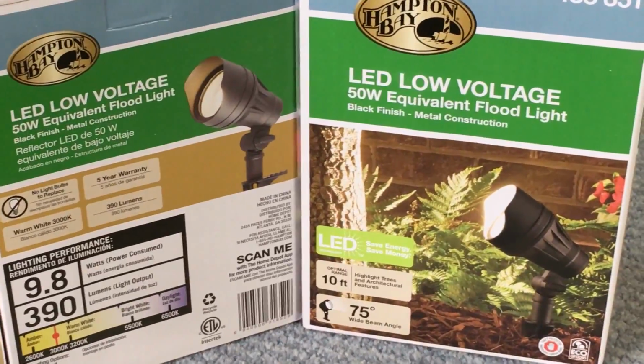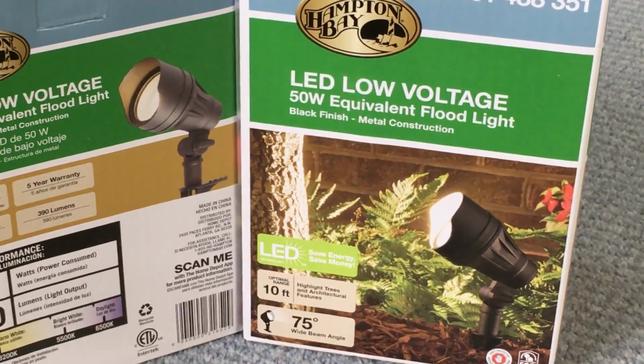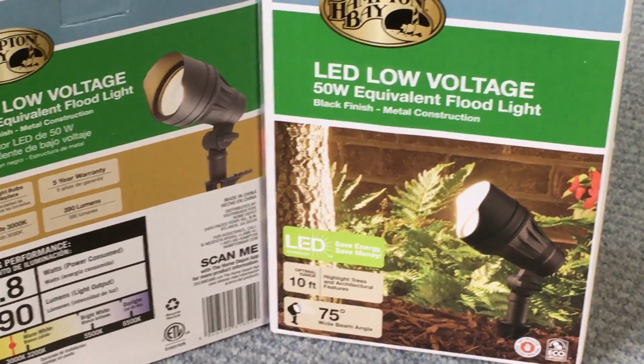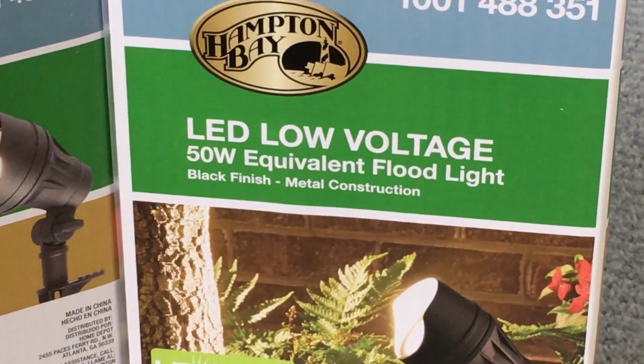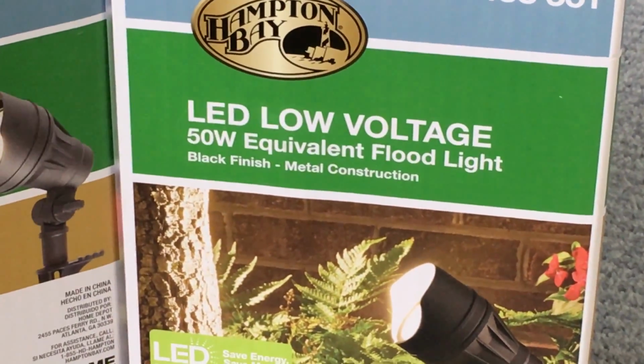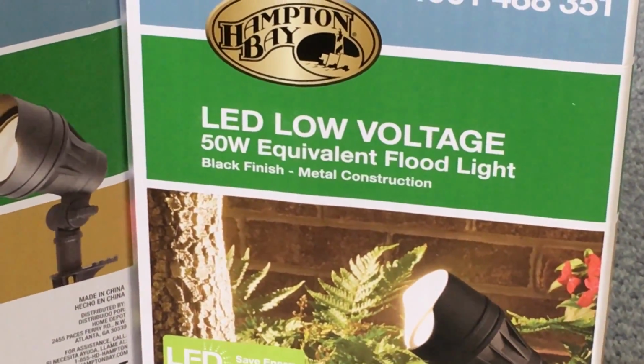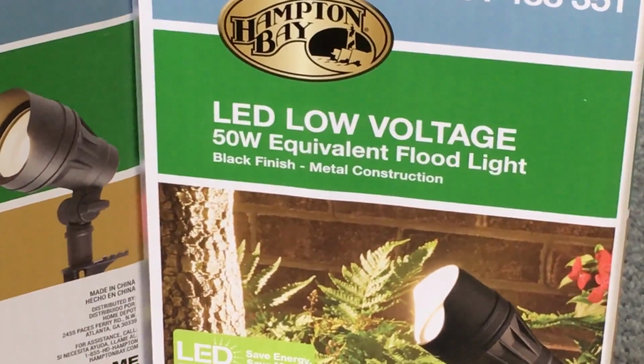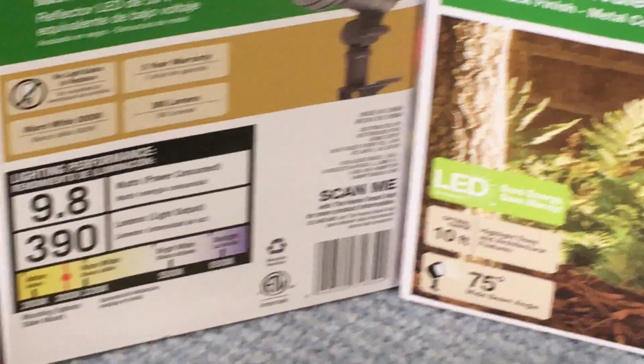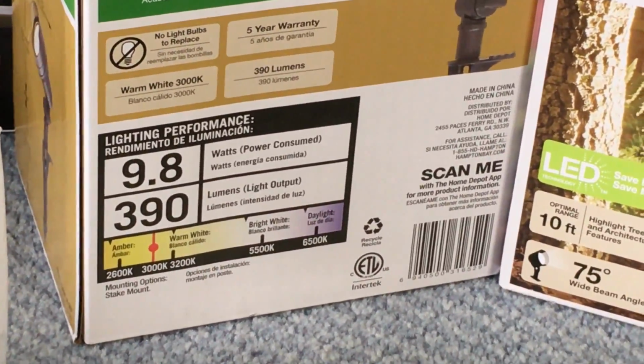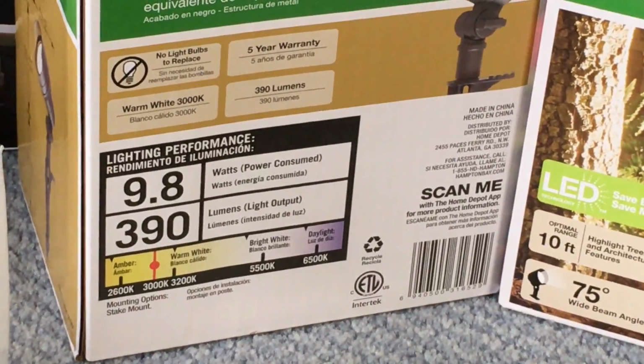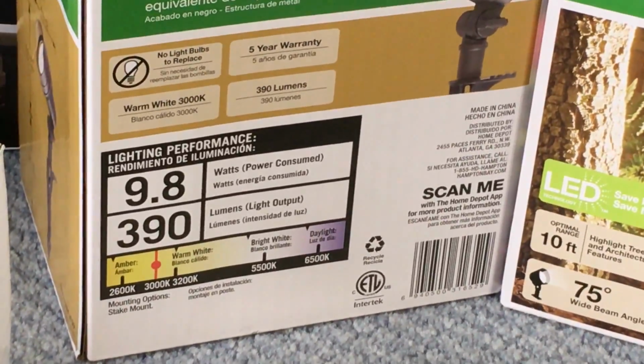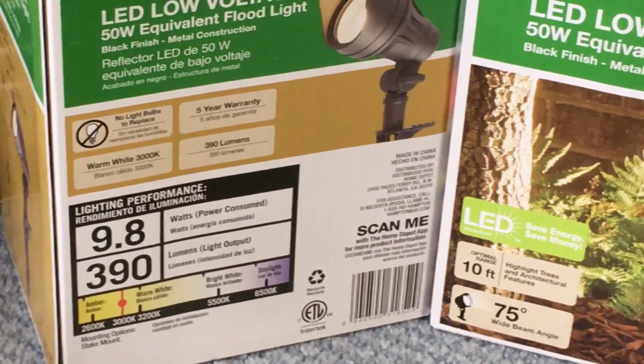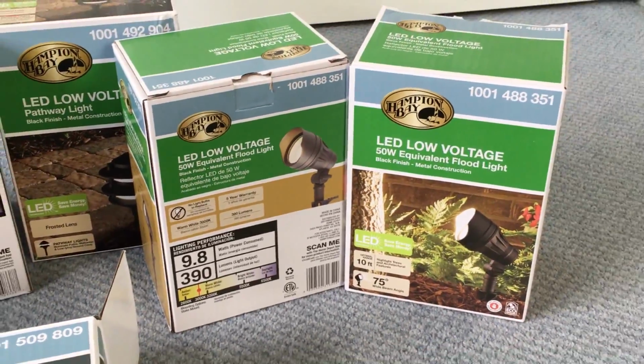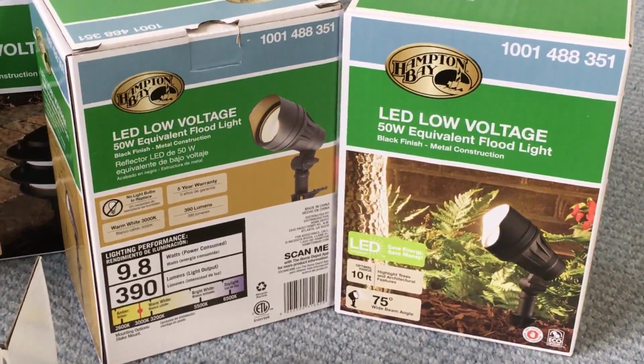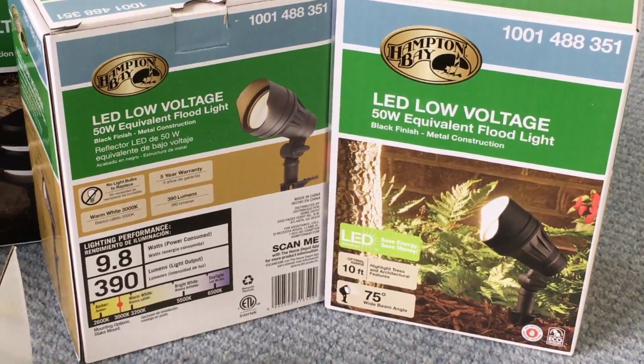This one is an LED low voltage 50 watt equivalent floodlight. Always remember, when calculating the transformer required, don't consider it as 50 watts. Always consider the actual power listed at the back, which is 9.5 to 9.8 watts. So if you're using two lights of this type, that's 9.8 times 2.